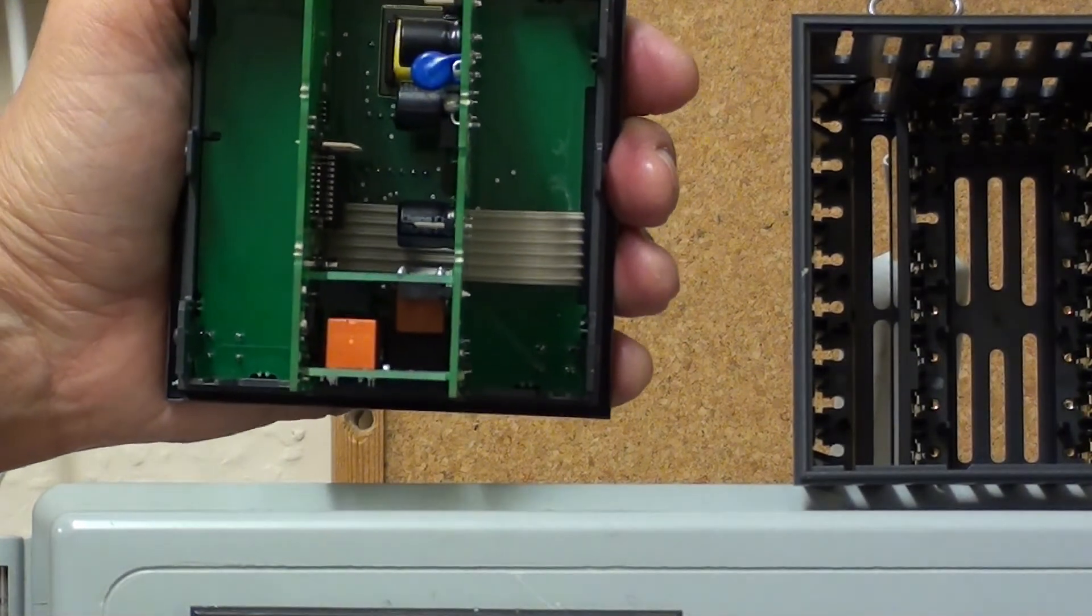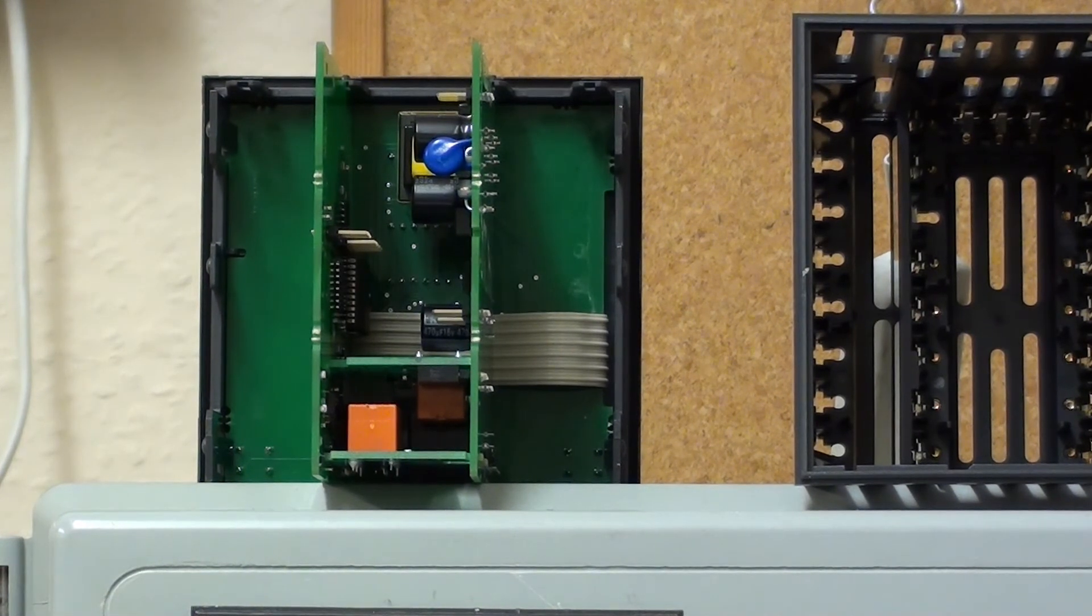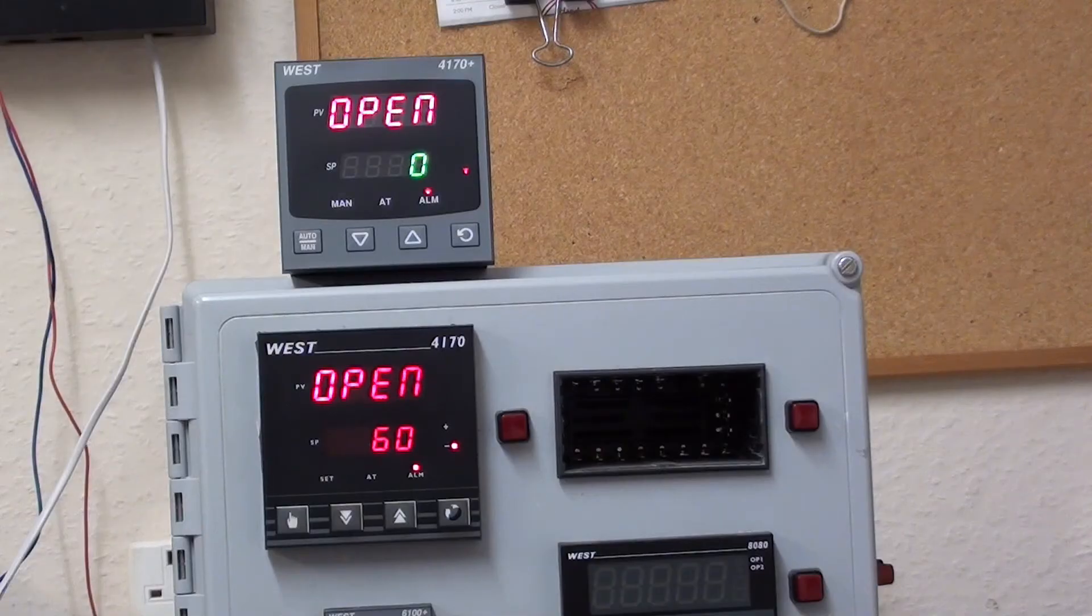Unlike the previous N4170, output 1 on the Plus series is a plug-in board. It's not a factory-built fixed board. With P4170, the option boards that are fitted inside the controller are auto-detected.